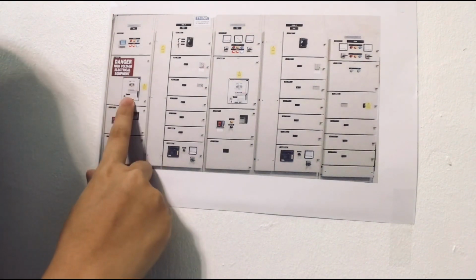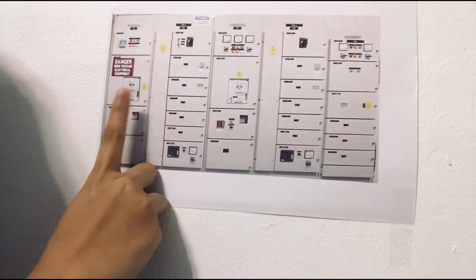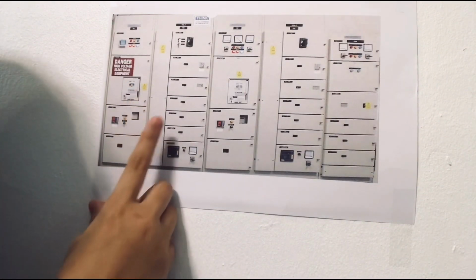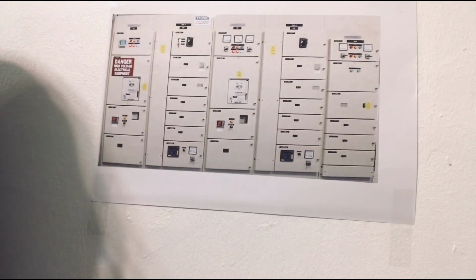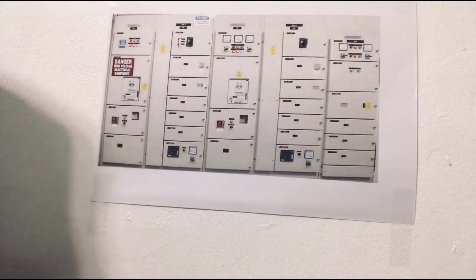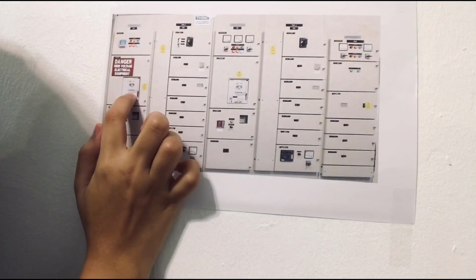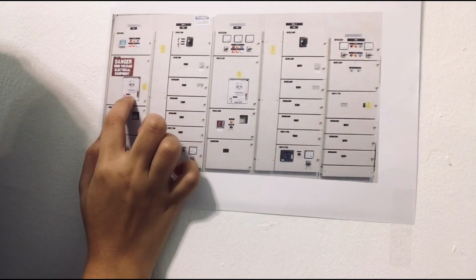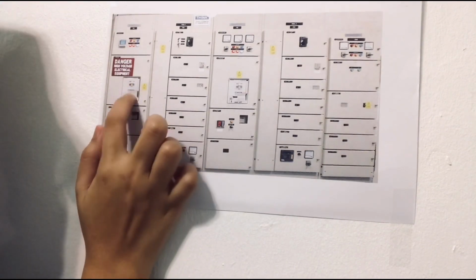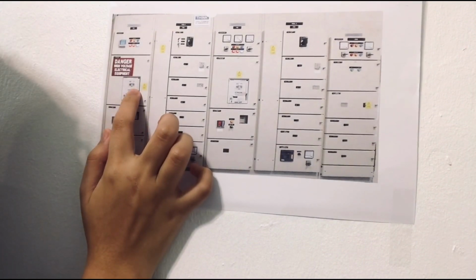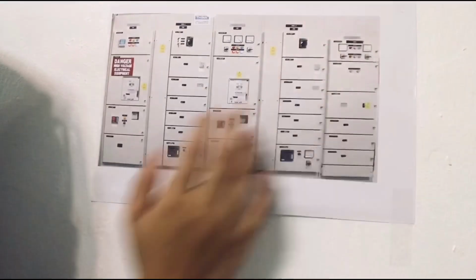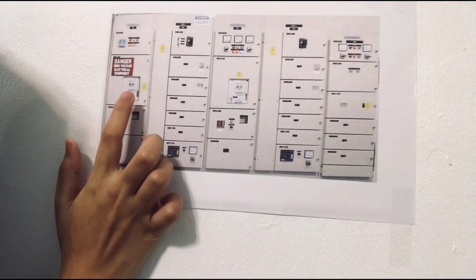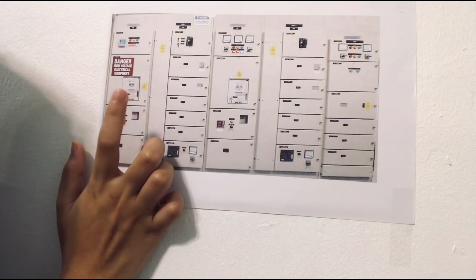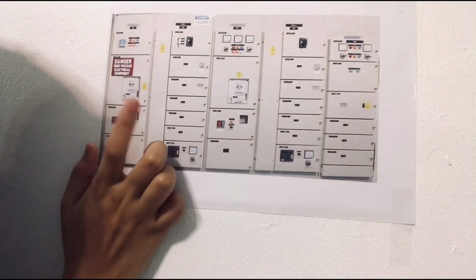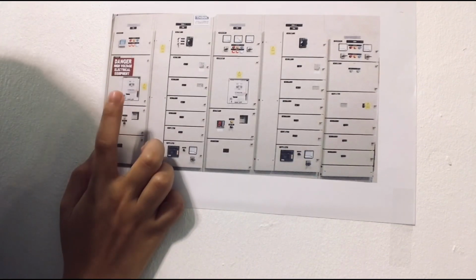In order to give a bus supply, we need to turn on the ACB. Before we turn on the ACB, we must make sure the coil is charged first. In this ACB, we have a coil, so we need to charge it before we turn on the ACB. In this panel, we can see either the ACB is charged or not. If not, we need to charge it manually, because the ACB coil takes time to charge automatically.